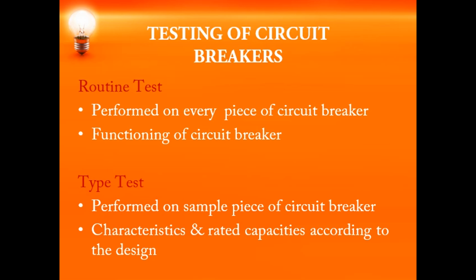Whereas a type test is performed especially in a high voltage laboratory, where, say you have 20 or 25 circuit breakers, out of that only 1 or 2 sample pieces will be tested. Okay, the type test is done mainly to confirm the characteristics and the rated capacities as per the design. So these are the main two testings which are being done on the circuit breaker.